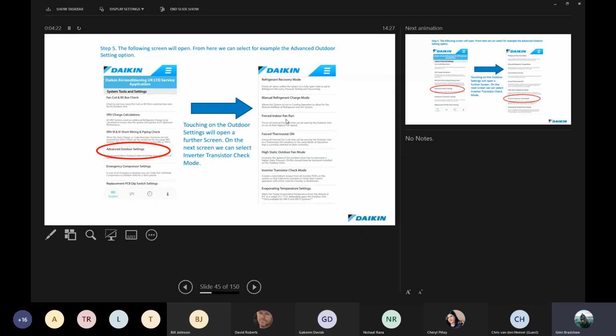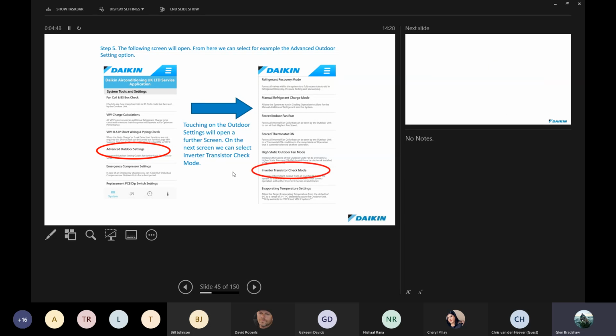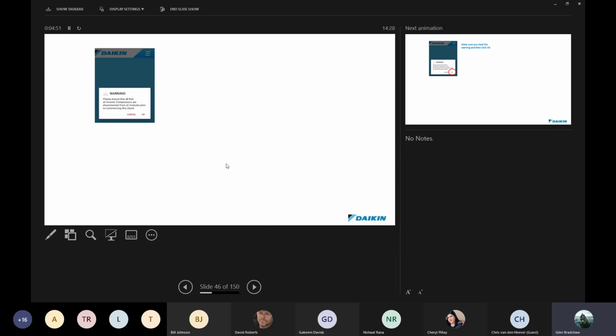Forcing of the indoor units is also very good if you've coded up a unit and you find that you're missing indoor units. By using this part of the app, you'll be able to turn on indoor units, and the ones that don't come on are the ones that the condenser cannot see. You can also see how to adjust the static pressure on the outdoor fan, the inverter transistor check modes, as well as adjusting evaporating temperature settings. If there are any warnings, please take note of them and adhere to them. They're there for both your safety and the equipment's safety.